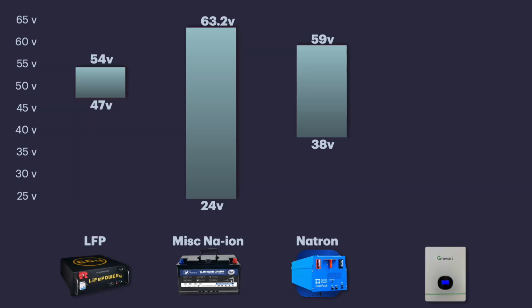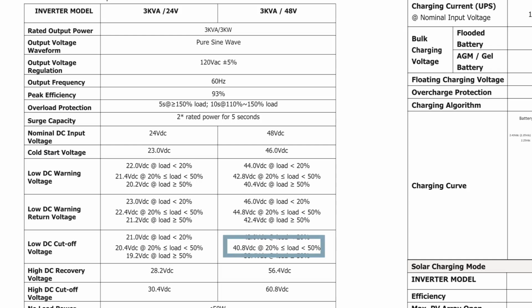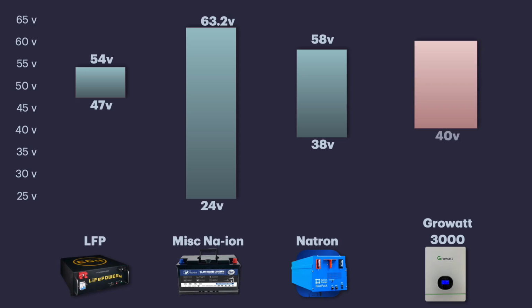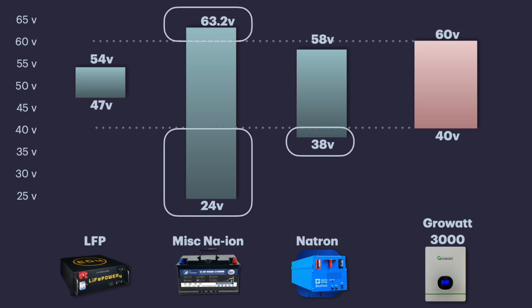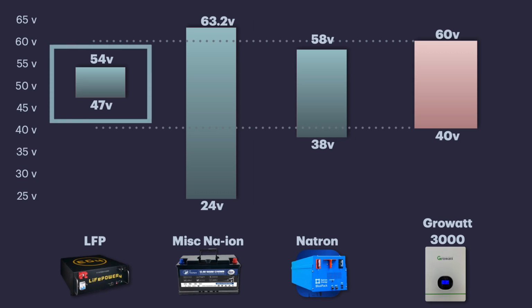If we use these batteries with existing inverters, in this case a Growatt 3000, the low DC cutoff is around 40 volts, while the high DC cutoff is around 60 volts. This is the voltage where the inverter will shut itself down to protect your batteries, so you can't use any voltages outside this range of 40 to 60 volts. These ranges are not usable for us with this inverter. As sodium batteries become more prevalent, inverter manufacturers will have to update their software to handle these wider ranges. The lithium iron phosphate battery is entirely within the range this inverter can handle.